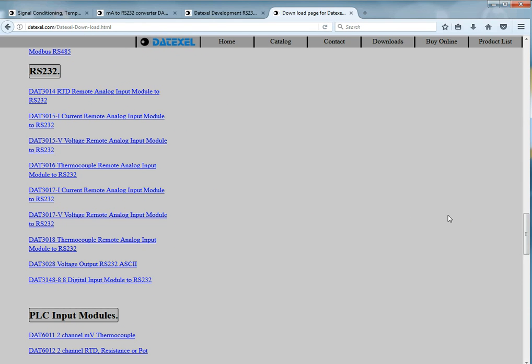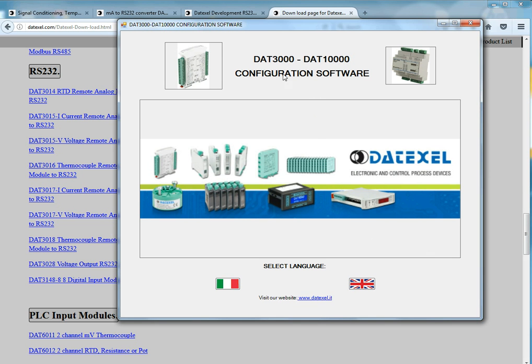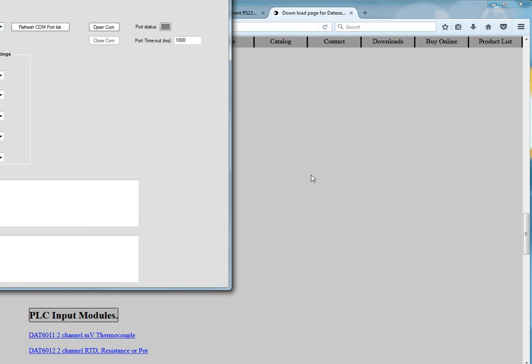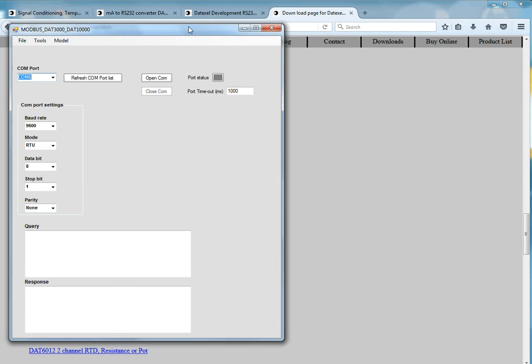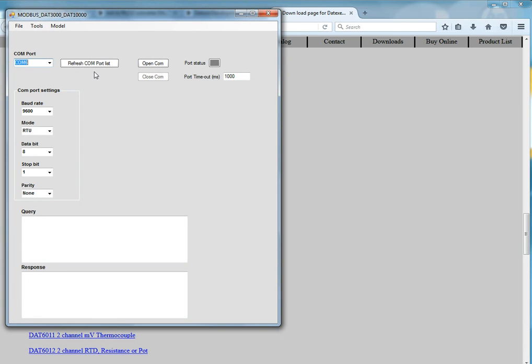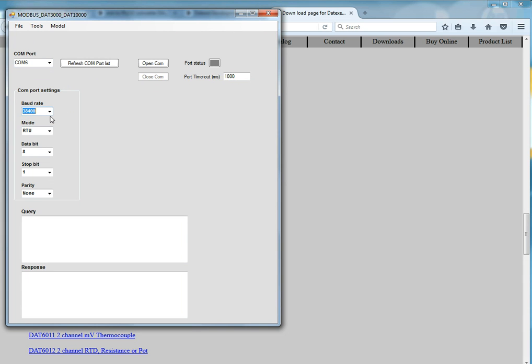The configuration software, we select English and it automatically finds the COM port which is connected to the hardware. You have to select 38,400 which is the default baud rate of the DAT3000 equipment unless you have asked for a different baud rate setting. That is the default.